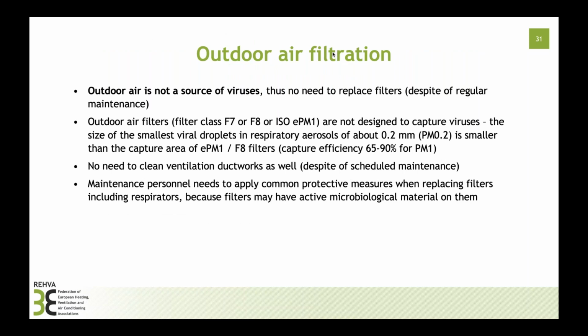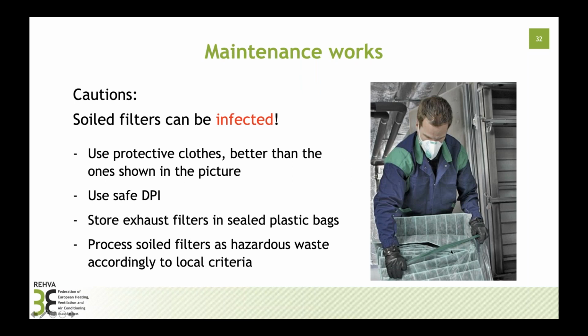And the same applies to outdoor air filtration, which basically is not important in this case, because outdoor air is not a source of viruses. But indeed, we need outdoor air filtration for other purposes: to protect the equipment, and to protect the occupants from PM2.5, so outdoor particulate matter. It also applies to filter replacement: common maintenance schedules and procedures should be applied. No extra filter replacement is necessary, but when it is an issue of maintenance personnel protection, they need to have relevant personal protection, because soiled filters really can be infected, and that's a risk during epidemic conditions, actually for any maintenance work.